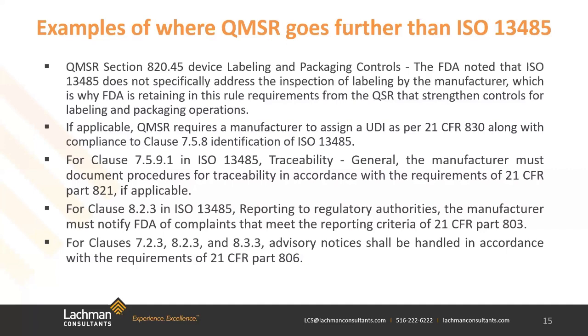7.5.9.1. The fourth bullet, we're talking about reporting to the regulatory authority. The manufacturer must notify the FDA of complaints that meet the reporting criteria of Part 803, which is medical device reporting, which is not changing. And that's along with the ISO clause of 8.2.3. And finally, advisory notices shall be handled in accordance with the requirements of Part 806, which is medical device reports of corrections and removals, along with those applicable ISO clauses.